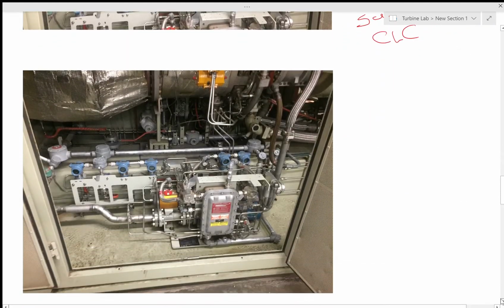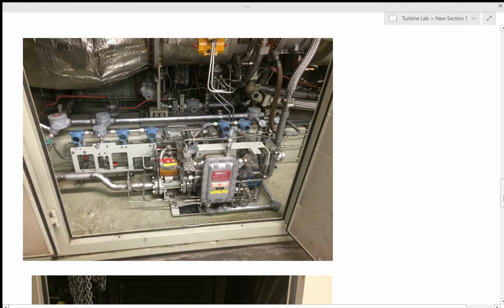Here are the natural gas controls that feed into the generator. We get natural gas at 150 psi and drop it down to about 120 psi before putting it into the turbine.